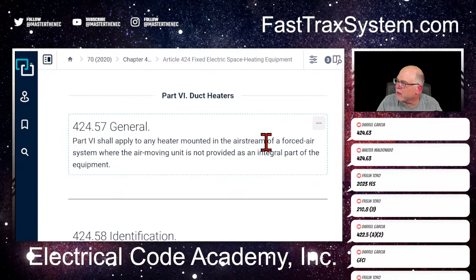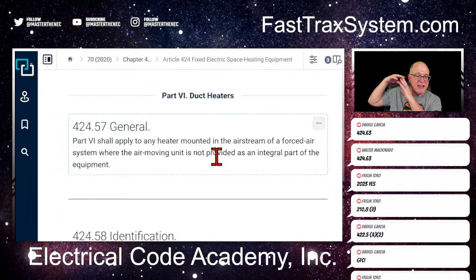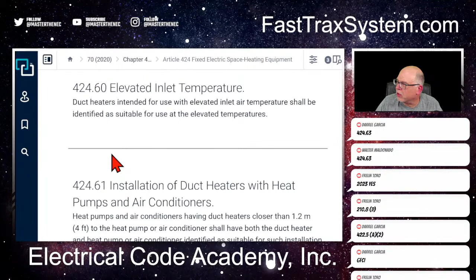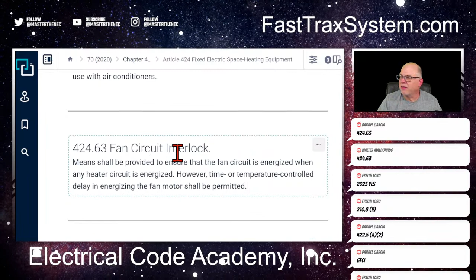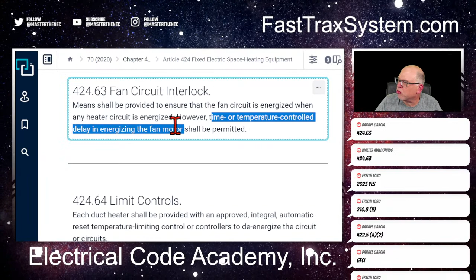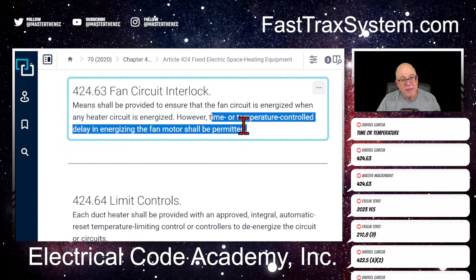Duct heaters apply to any heater mounted in the airstream of a forced air system where the air-moving unit is not provided as an integral part. Again, you've got the duct system and the fan that's blowing it. So we go look down at interlock — we know what interlock means. The whole question is determining whether or not, when the heater circuit is energized, the fan can be delayed or not. And here's what it says: means shall be provided to ensure that the fan circuit is energized when any heater circuit is energized. However, time or temperature controlled delays in energizing the fan shall be permitted.